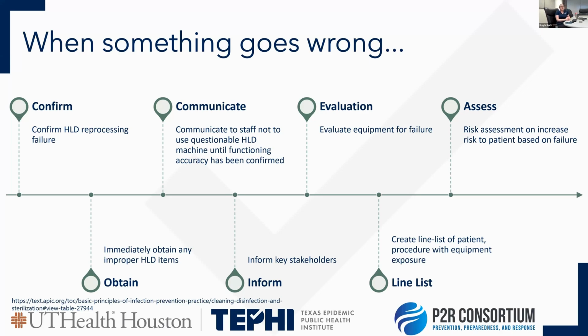So if something does go wrong with your scopes, the first step is to really confirm there has been a failure, so that you have confirmation that either one cycle with one device or that whole system has failed in something. Next, you want to obtain any improperly high-level disinfected or cleaned items. So if you know that your AER failed, go to your logbooks and see what scopes were processed on that day and then obtain them. Take them out of service until you know what the next step is.